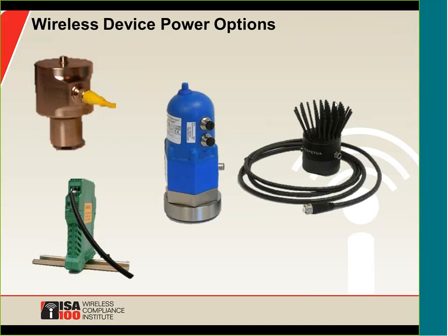Okay, so now you've made the jump into wireless. One of the considerations there is how long are these wireless devices going to perform without needing attention? Specifically, how long does the battery last in them? Depending on how rapidly the data is being collected from the wireless device, the battery life can be anywhere from 3 to 6, 3 to 8 years, something on that order.